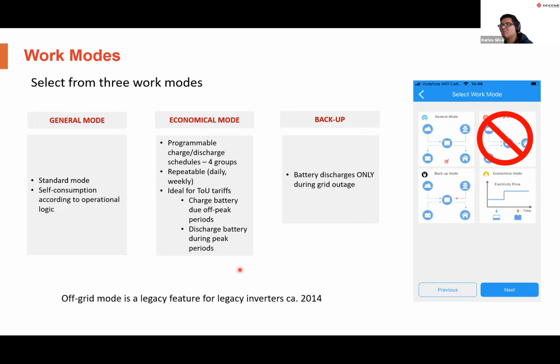So this means that you can charge the battery from the grid at periods of low cost of electricity, so in your off-peak periods, and you can discharge the battery during the peak periods where the cost of electricity is very high. In terms of the backup mode, the backup mode is basically a mode where the battery will not discharge. The battery will only discharge when it goes into backup mode. So it will not discharge the battery in normal operation. However, in the general mode, although the battery is being discharged and charged frequently, depending on what's happening on the loads and what's happening on the PV panels, in general mode, you can still set the backup function by going into the advanced settings. So even in the general mode, if there's a grid failure, the system will still be able to continue to power the backup loads.